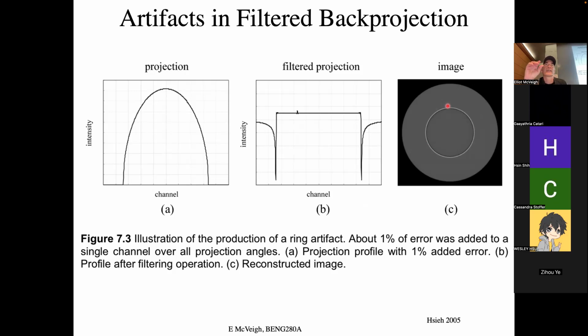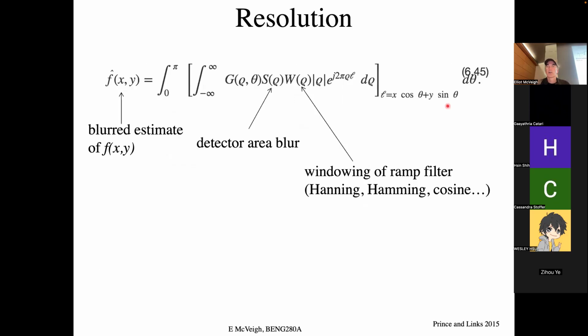Even when you calibrate the scanner, when you get down to really, really low numbers of photons and you look at the center of your image, you see these faint circles, right? Because to calibrate the detectors so that they're right on the money every time and not just a little bit off for their gain is really difficult. That's why they calibrate these things every day, because these small percentages that are constant are a source of these strange artifacts. So you'll see this towards the center often where you have really low signals.